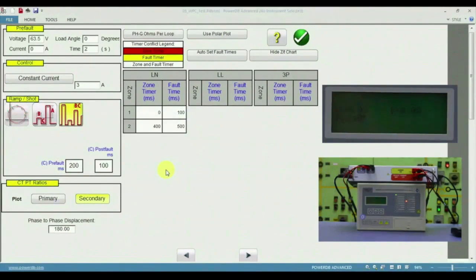So if this is true, then it creates 2 more points which are nearer to the boundary. Let us say I create 1 point at 10 ohms and 1 point at 0. So the test kit will inject an impedance at 10 ohms, there is no operation, and at 0 there is an operation. So now assume that the boundary is 5 ohms.